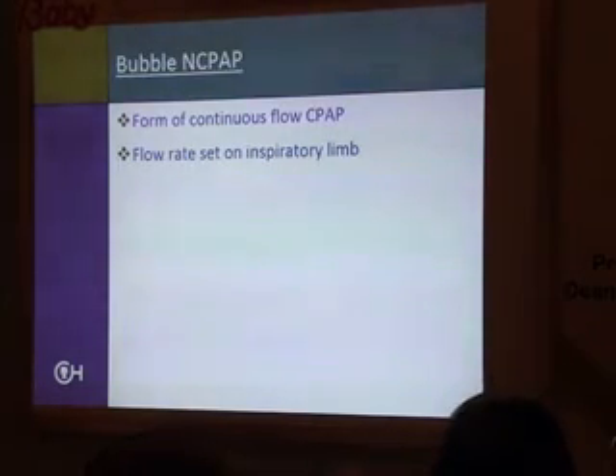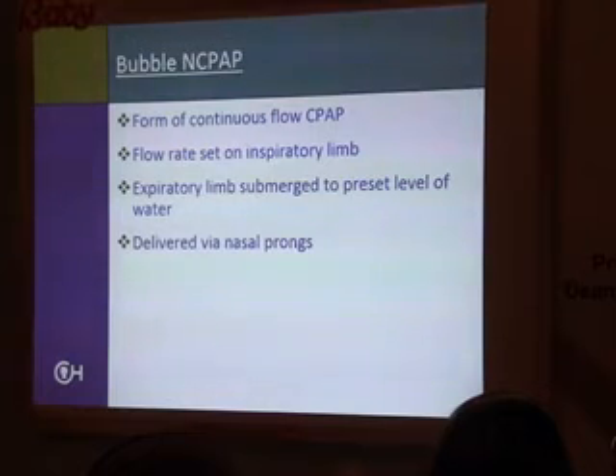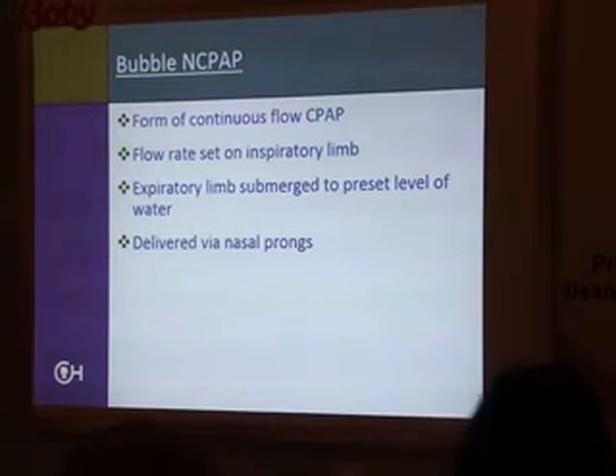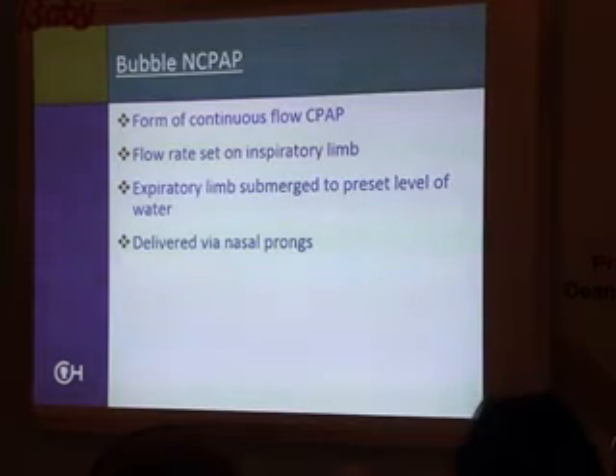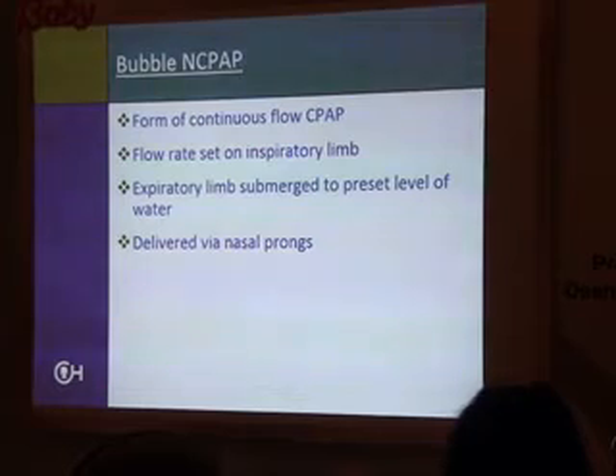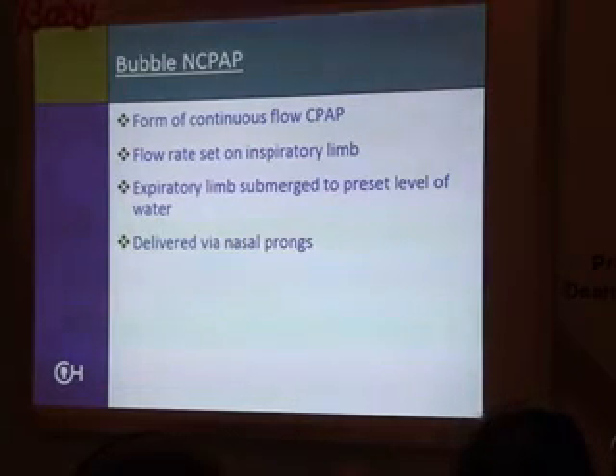Bubble CPAP, again, this is a form of continuous flow CPAP. It provides a flow rate at the inspiratory limb, and then your expiratory limb is placed and submerged to a preset level in water. It's delivered predominantly via short nasal prongs. However, since it's kind of come back into phase, and CareFusion started selling a device, there may be a different company that you all have here that sells a bubble CPAP device. They've also provided masks now, which helps you do that change back and forth. The negatives with this is there's no readout, there's no alarms whatsoever. You have no idea if what you have set via a water column is actually what you're getting, and you have no idea if you have a leak or if you're not achieving it.